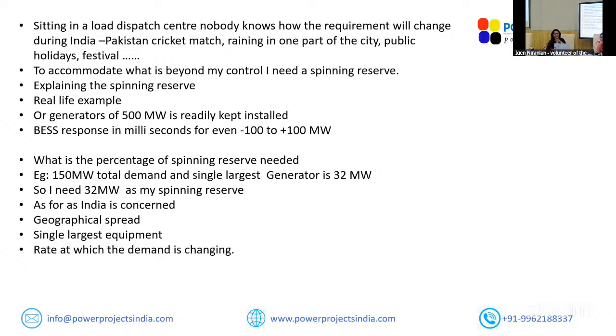So I just finished explaining what spinning reserve is. If it's a country with, say, 150 megawatt capacity, and the single largest generator in that country is generating 32 megawatt, then if that generator goes off, what is the spinning reserve requirement? It's 32. So it depends on the country's requirement and the single largest generator.